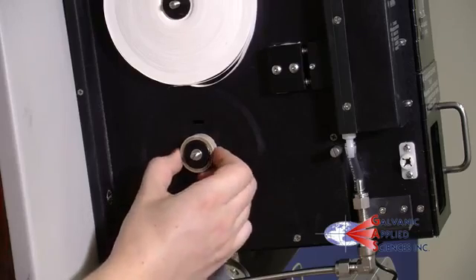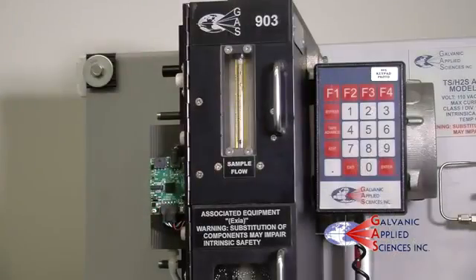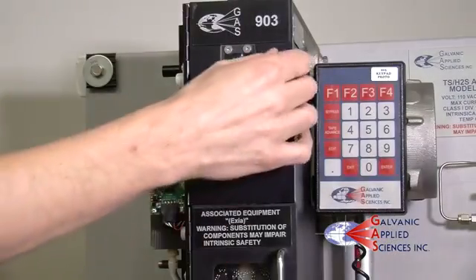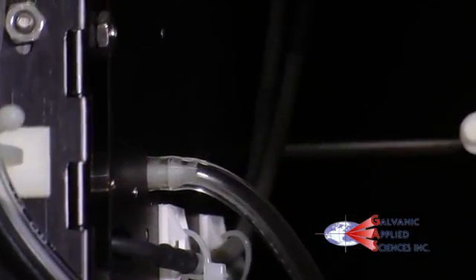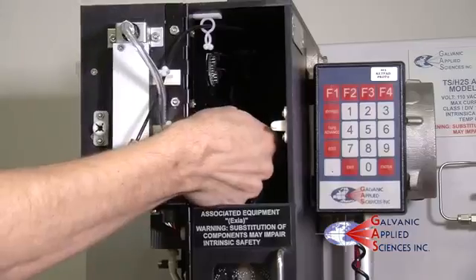When changing the tape, we recommend cleaning the sample chamber sensor before a new tape is put in. Begin by opening the top hatch of the analyzer and detach the tubing that flows from the humidifier to the sample chamber.